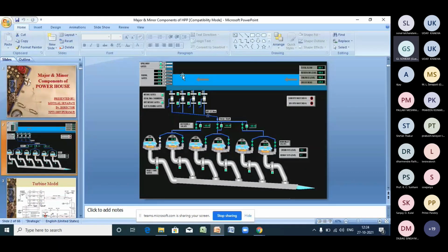So that back pressure will follow the pressure shaft path, and it will be released in the surge shaft. So when you are operating the power plant and stopping the power plant, the surges will be handled by the surge shaft. That's why fast water is coming to the surge shaft. When you stop it, the water goes to the surge shaft. Meanwhile, when you start the machine, the surge shaft level goes down.